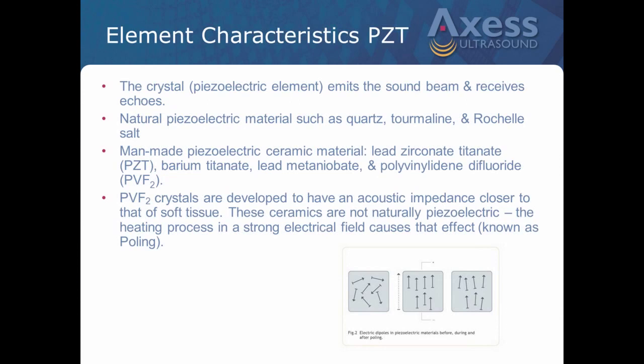Now, one of the things about PVF arrays is they've been developed to kind of match the acoustic impedance of the human body, and closer to that of the soft tissue. So obviously, from a sound perspective, if the impedance of the probe is closer to the impedance that your body naturally produces, basically the better image quality you're going to get, the less signal loss and so on. The only problem with PVF, and I've got a little picture here to show you down in the corner, is that those materials are not naturally piezoelectric. So you have to use a process called poling, and I'll get into poling a little bit later, but it just gives you an example. It's a process that the manufacturers of the array have to go through in order to turn those crystal arrays into a natural piezoelectric property so that they can transmit and receive ultrasound.